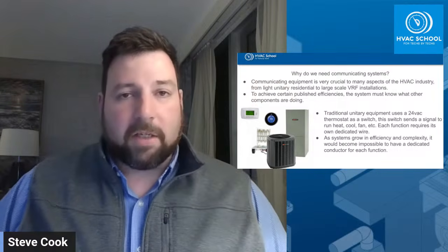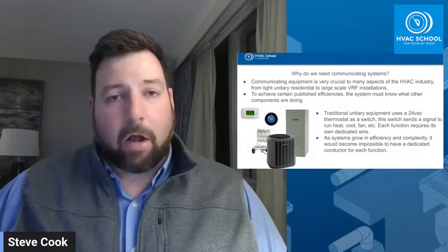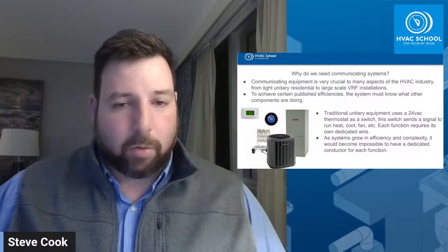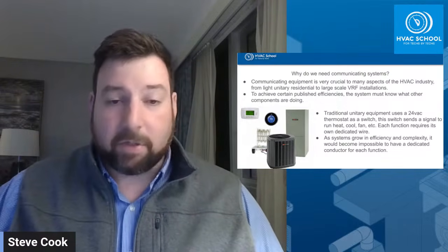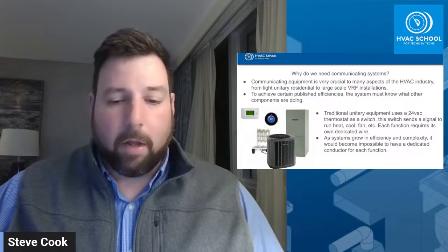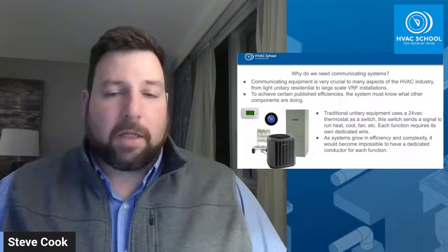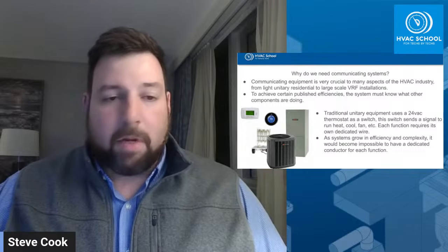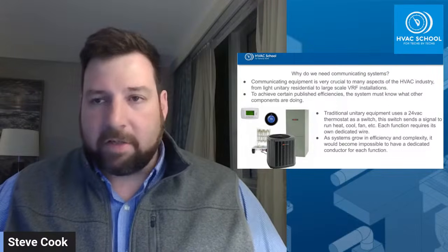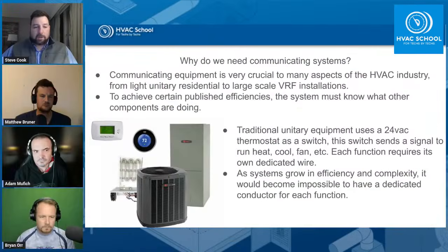In a communicating system, it would see these conditions. It would either back off, do what it needs to adjust accordingly, or in the case that something's wrong, it could throw a fault or an alarm. But in these cases, when you look at a mini split or VRF system, the outdoor unit has to communicate with the indoor unit in order to get to these efficiencies. So let's say we want to run the compressor faster, or we need to slow it down - we need to see what's going on inside the system, and a 24 volt AC control cannot do that for us.